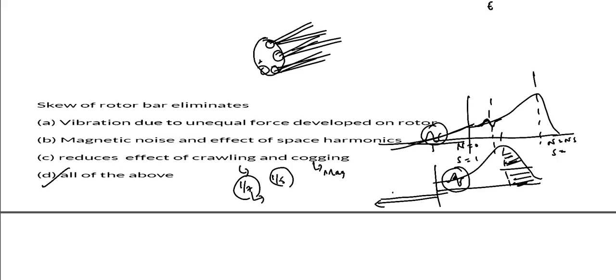Some inclination makes the magnetic flux distribution sinusoidal, and also gives mechanical balance. So to reduce the magnetic noise and the effect of the space harmonics, these will reduce due to the skewing of the rotor slots. Okay, that also reduces the cogging and crawling.